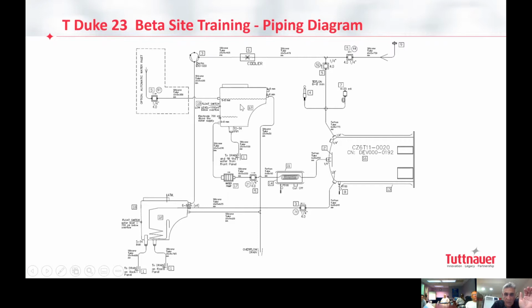So, one tank, mineral-free water, waste tank, steam, the chamber itself. We have the steam generator slash vaporizer, where we're generating the steam to fill into the chamber. You will soon see how it works exactly. And we have the vacuum system in the top with its own chiller, heat exchanger. Here you can see the air filter. So once we start the cycle, what happens is the vacuum pump starts running, the chiller starts running, and this valve, the 52 valve, opens.